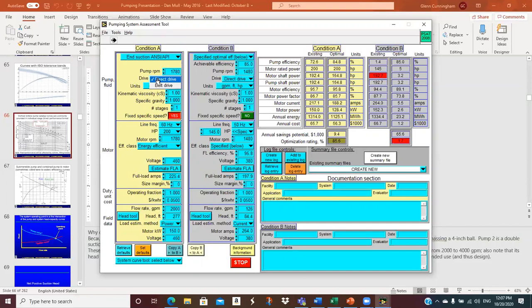We can run direct drive, where the pump and the motor are coupled together, basically the same shaft, or you have a belt drive. And if you have a belt drive, you have belt losses, and this has a fairly typical curve built into it to predict the belt losses. That would be part of the energy use in the system. Kinematic viscosity in centistokes: what fluid are you pumping? Specific gravity: what fluid are you pumping? Number of stages: generally you probably have a single stage pump, but you could easily have a 5-stage boiler feed water pump.